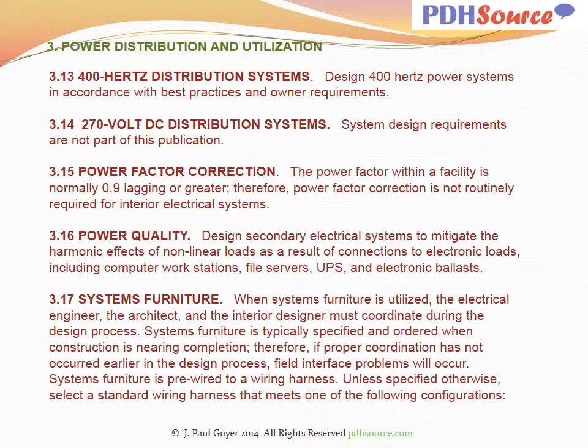With regard to systems furniture, when systems furniture is utilized, the electrical engineer, the architect, and the interior designer must coordinate during the design process. Systems furniture is typically specified and ordered when construction is nearing completion. Therefore, if proper coordination has not occurred earlier in the design process, field interface problems will occur. Systems furniture is pre-wired to a wiring harness.